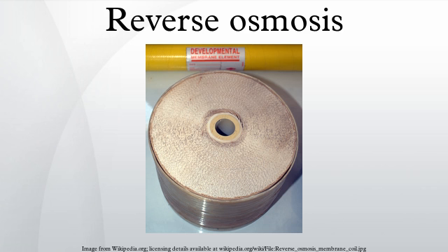Devices used, in order of invention, are: turbine or Pelton wheel, a water turbine driven by the concentrate flow, connected to the high-pressure pump drive shaft to provide part of its input power. Positive displacement axial piston motors have also been used in place of turbines on smaller systems.